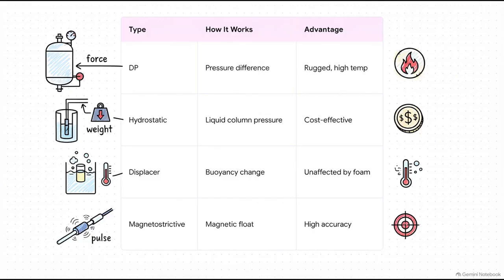Next up are displacers. These rely on buoyancy. As the liquid rises, the displacer floats, which is awesome because it makes them immune to annoying variables like foam or temperature swings. Finally, magnetostrictive transmitters. These use a magnetic float riding along a waveguide. A pulse is sent down, and the physical twist in the waveguide gives us a ridiculously accurate continuous measurement. They literally feel exactly where the liquid is.